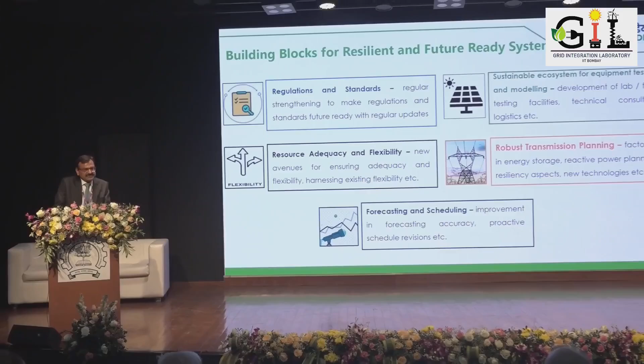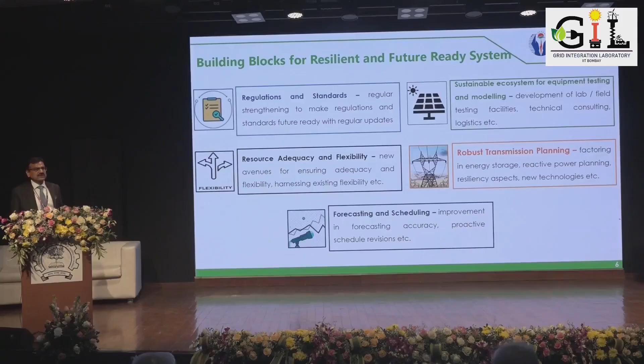So it ramps from 0 to 50 gigawatt. It starts ramping after the sun comes up, which nowadays is after 7, so from 7 to 11 it will be ramping to 50 gigawatt. But this ramping is important. If there is any delay in this 50 gigawatt ramp from solar, you will have a lot of issues in the system, and low frequency. And if it comes up high while you have taken other resources online, you will not be able to back them down, because there could be ramping constraints in bringing them down. So that is another challenge. Therefore, forecasting the renewables is becoming extremely important. All the OEMs, all the developers, everybody has to pitch in.